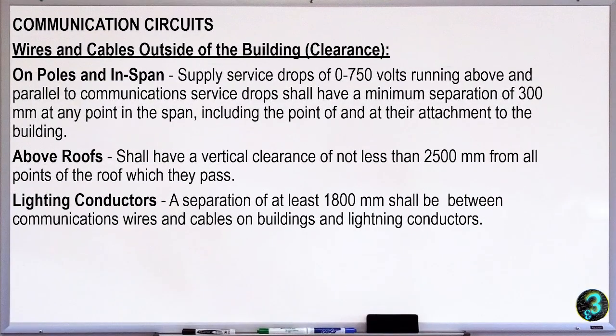Okay, so we have communication circuits, so wires and cables outside of the building clearance. So it is the same communication system na natackle natin during our discussion in PEC Part 2, no, the clearances between the power conductor and the communication conductor, same, no?